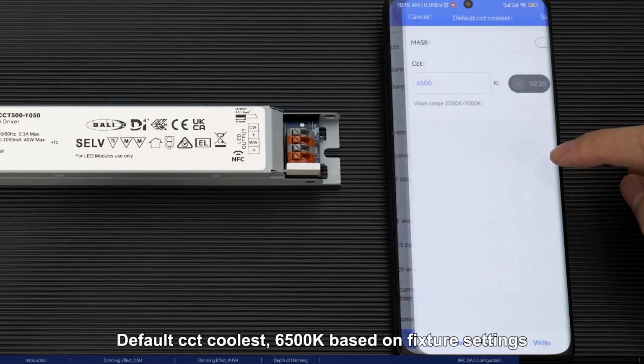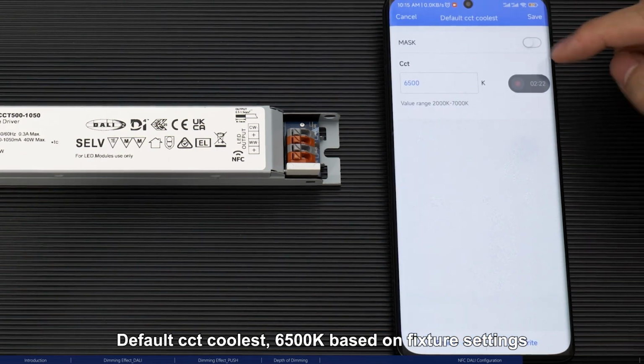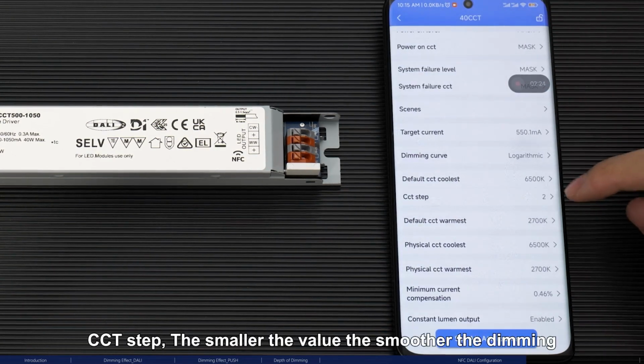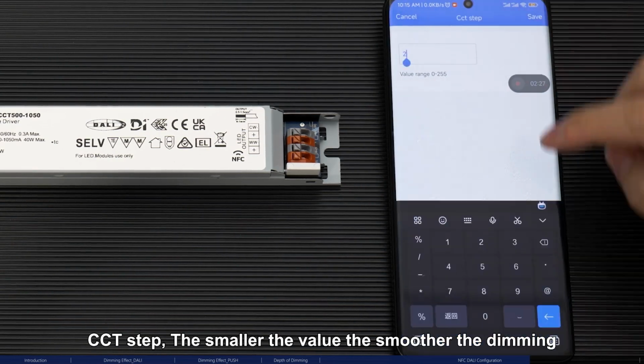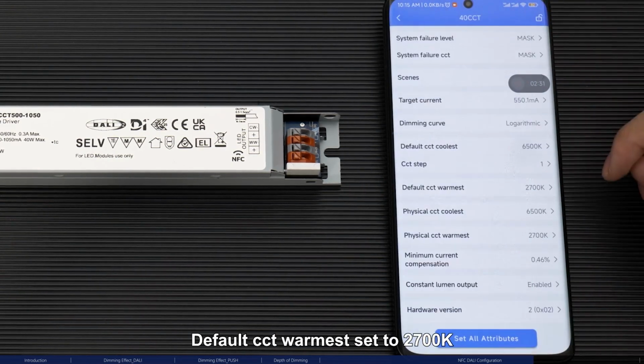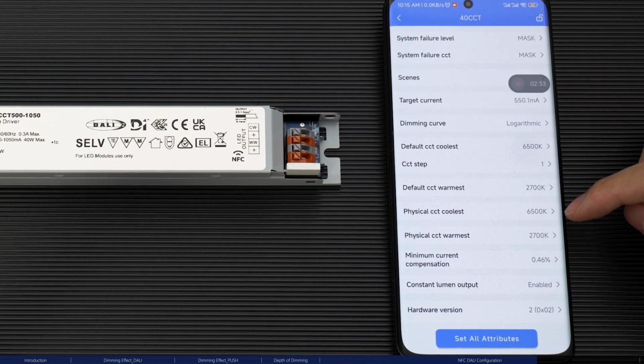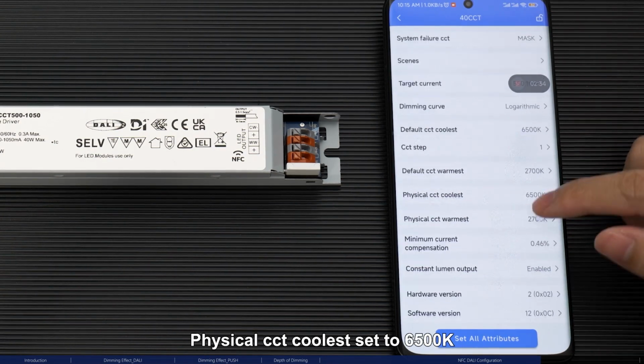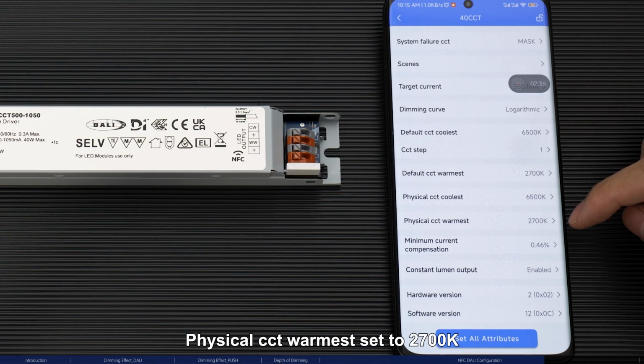Default CCT coolest, 6500K based on fixture settings. CCT step, the smaller the value the smoother the dimming. Default CCT warmest set to 2700K. Physical CCT coolest set to 6500K. Physical CCT warmest set to 2700K.